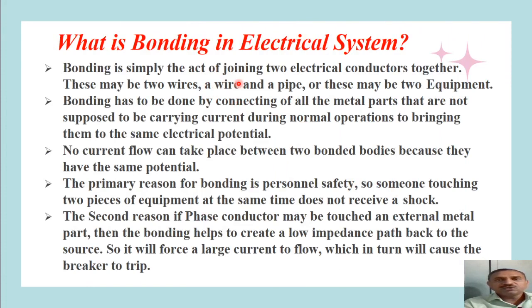Bonding is nothing but the act of joining two electrical conductors together. Now these two conductors can be from the wires or a wire and pipe, or there can be two equipments which are operated from a supply systems whose body are to be connected together. So bonding is nothing but connecting all metal parts that are not supposed to be carrying any current during normal operations to bring them to the same electric potential. By bonding, we are making that electrical equipments enclosures to be held at same potential. In such case, no current will flow between two bonded bodies because they will be held at same potential.